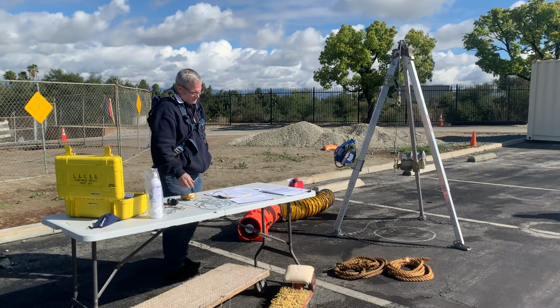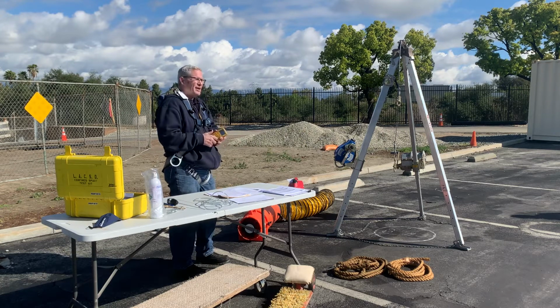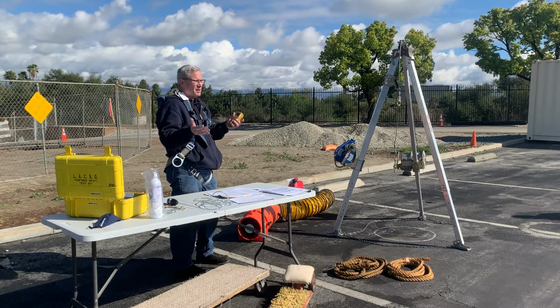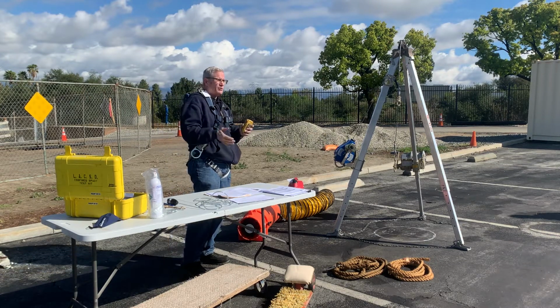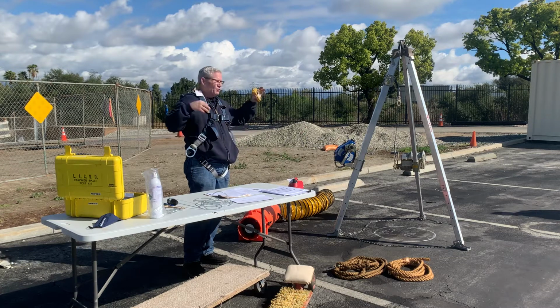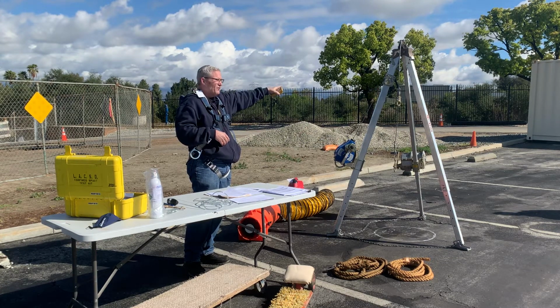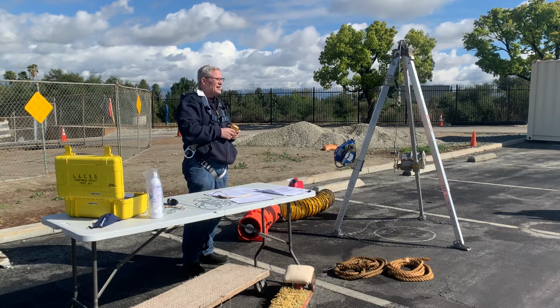In the operation of it, they have to be calibrated every 180 days, roughly 6 months. Part of the startup sequence tells me how many days are left on the calibration. They go into dock stations called MicroDock 2 stations, which are throughout the districts. There's one here at San Jose Creek, one at San Gabriel Valley Field Office. I know Valencia, Palmdale, Lancaster, and of course Carson have them.